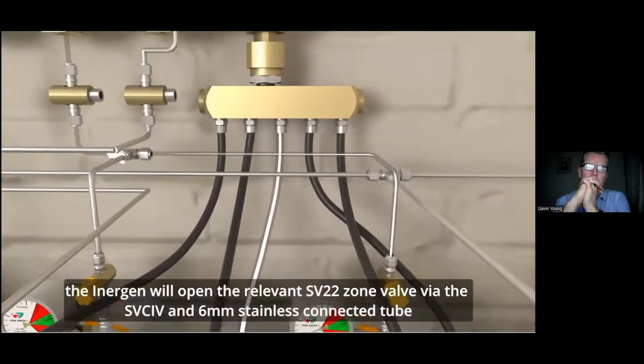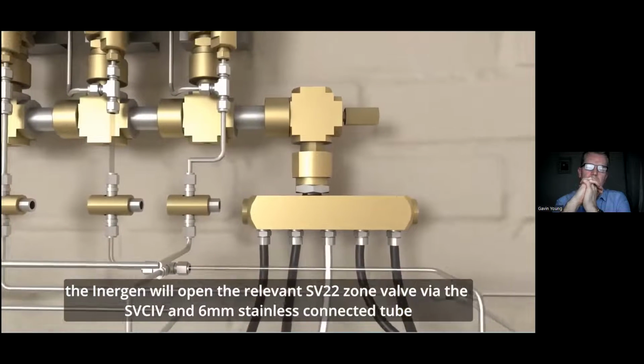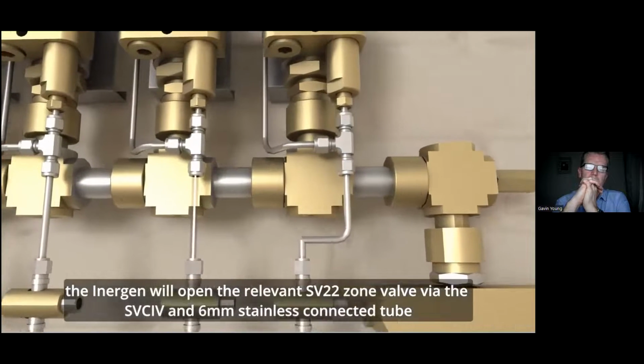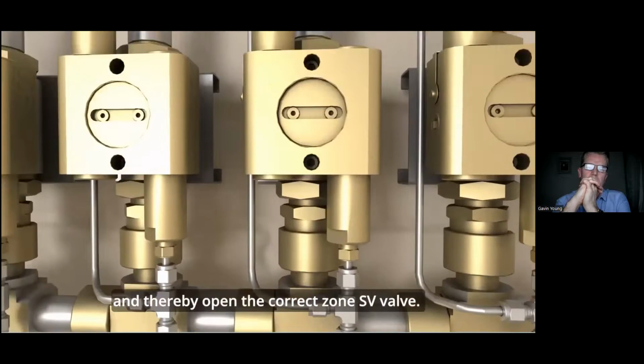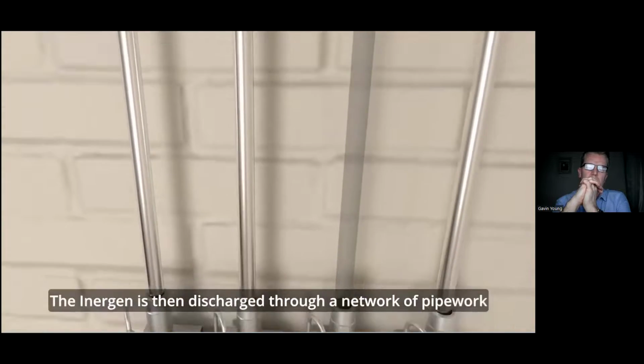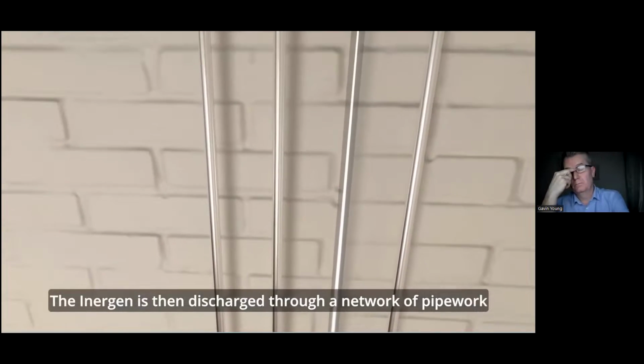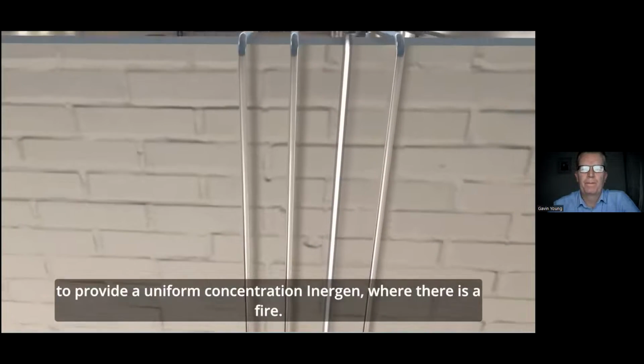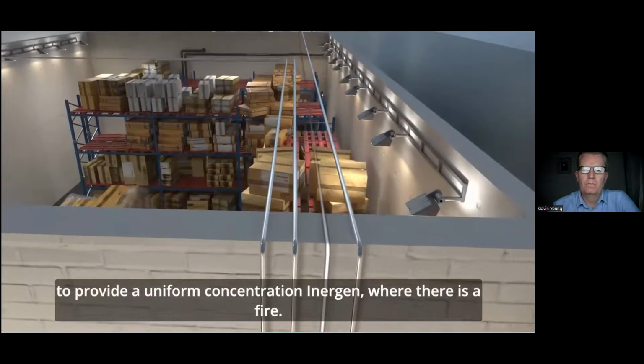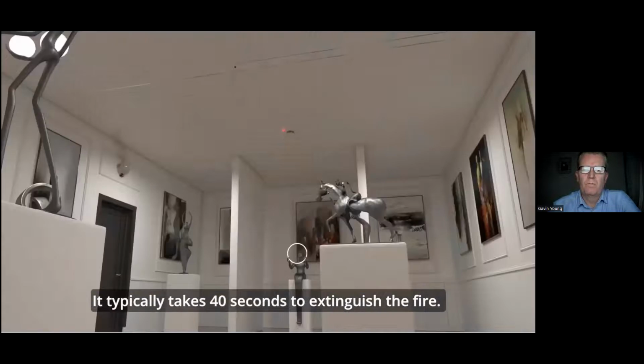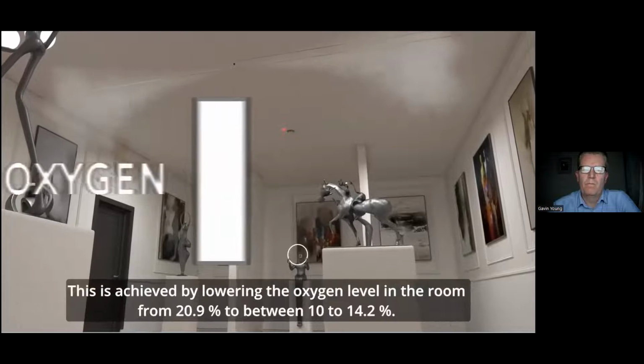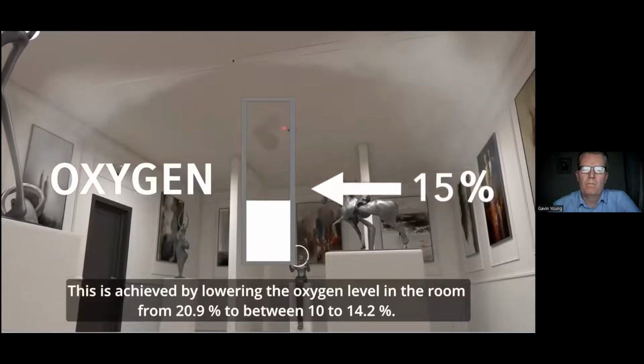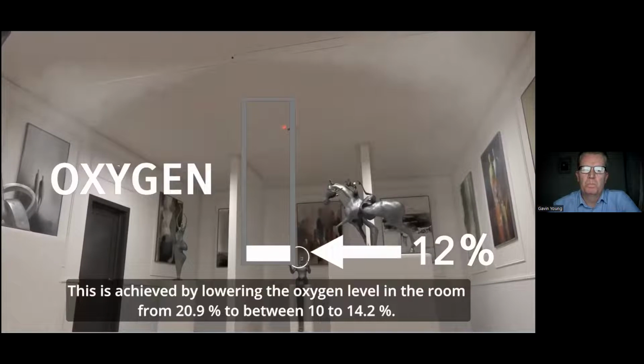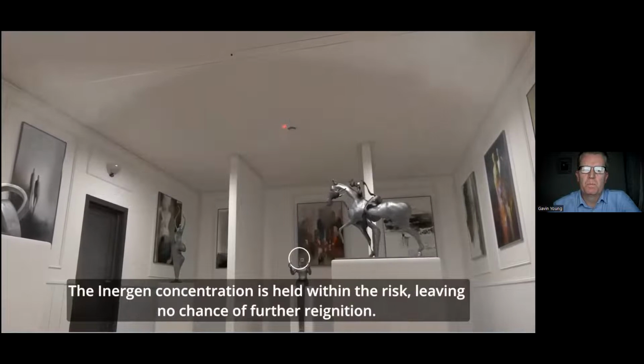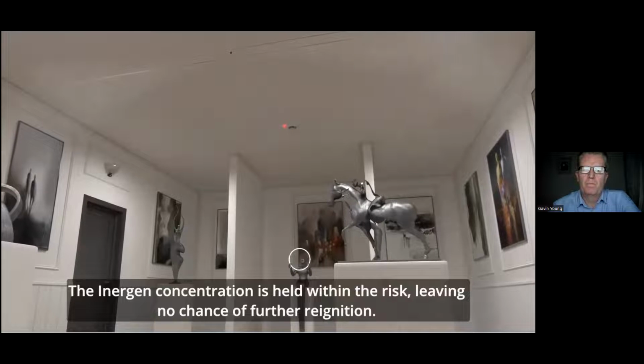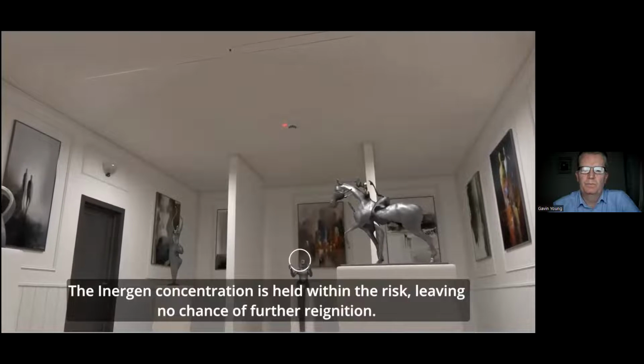The Inergen will open the relevant SV22 zone valve by the SV CIV and 6mm stainless connected tube, and thereby open the correct zone SV valve. The Inergen is then discharged through a network of pipework to provide a uniform concentration of Inergen where there is a fire. It typically takes 40 seconds to extinguish the fire. This is achieved by lowering the oxygen level in the room from 20.9% to between 10 to 14.2%. The Inergen concentration is held within the risk, leaving no chance of further reignition.